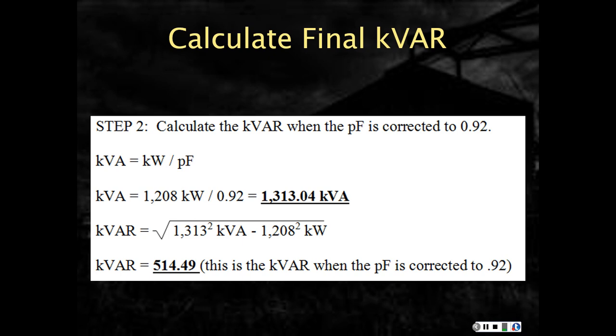Step 2, we need to calculate the future kVAR. In other words, what will the kVAR end up being if I have a power factor of 0.92? So again, we follow the same steps as in step 1. We first calculate the kVA because we know the kW, that hasn't changed. The power factor is going to be our new power factor of 0.92. We divide the two to get kVA. We solve for the new kVAR. So the kVAR now has dropped to 514.49. Again, that's the kVAR when the power factor is corrected to 0.92.